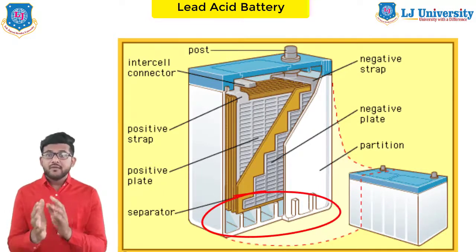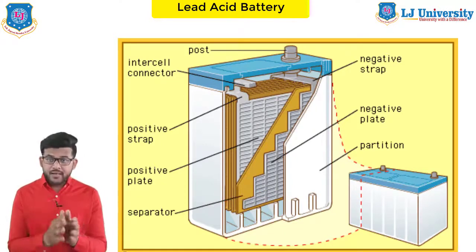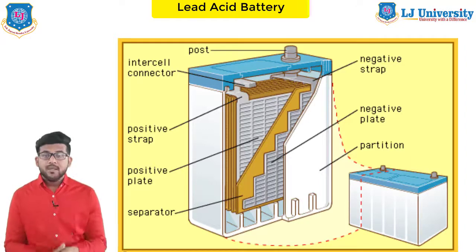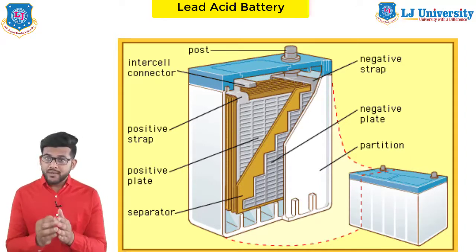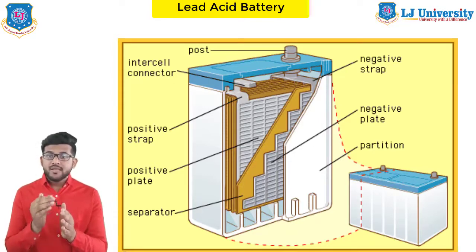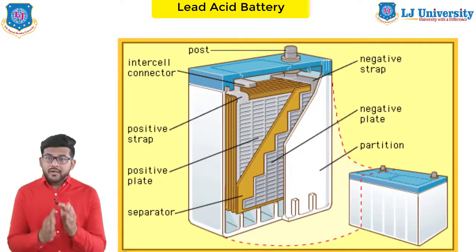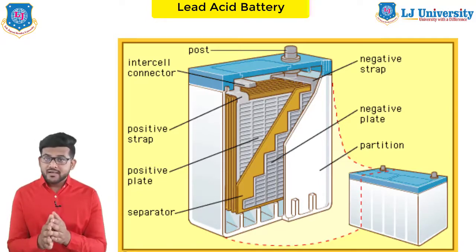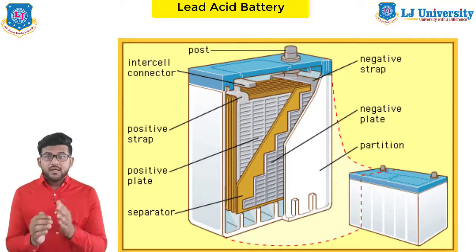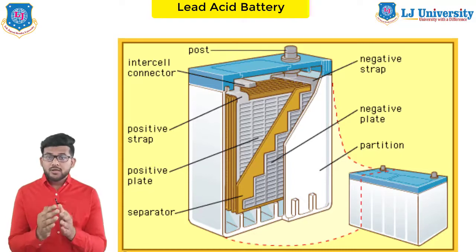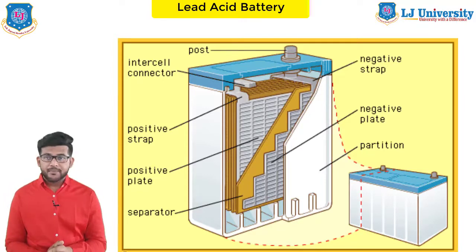At the bottom of the container there are four ribs. On two of them rest the positive plates and on the others the negative plates. The ribs serve as support for the plates and at the same time protect them from short-circuiting between the negative and positive plates. The material of which the battery containers are made should be resistant to sulfuric acid. It should not deform or be porous or contain impurities which could damage the electrolyte.